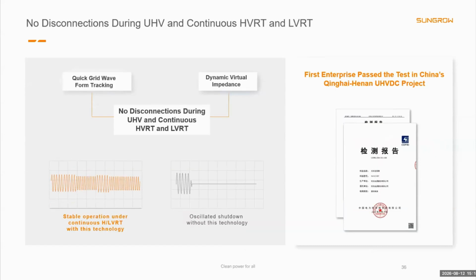The OnePlus-X solution can remain stable during continuous high or low voltage ride-through events. Fast waveform tracking and dynamic virtual impedance help avoid oscillation and disconnection. The objective is clear. When the grid is under stress, the inverter should remain connected and support recovery.